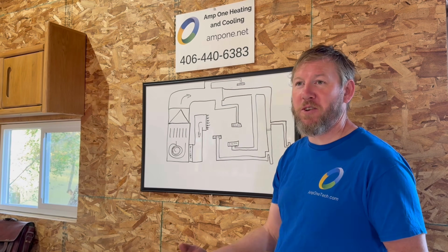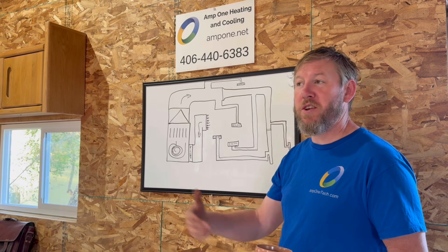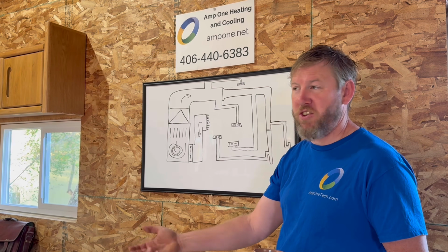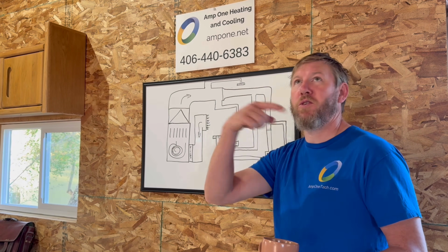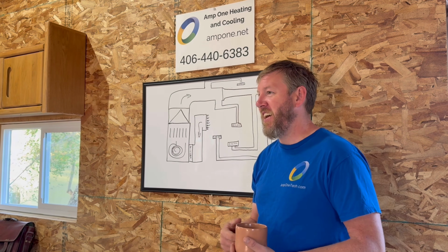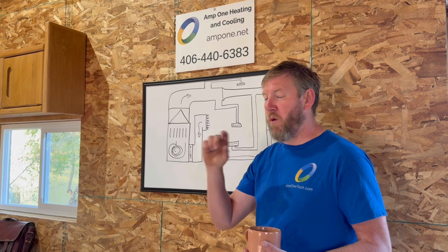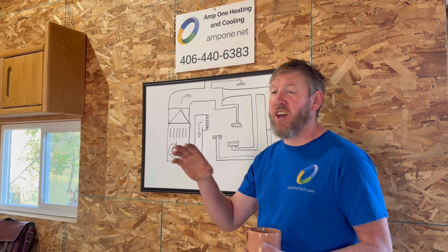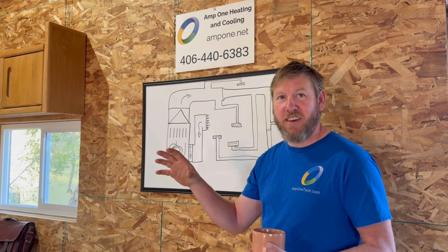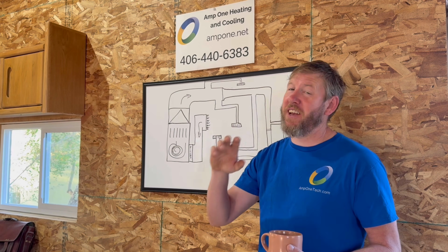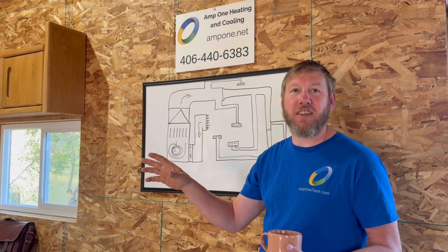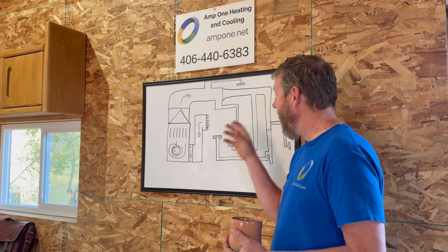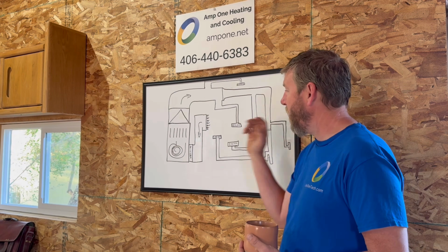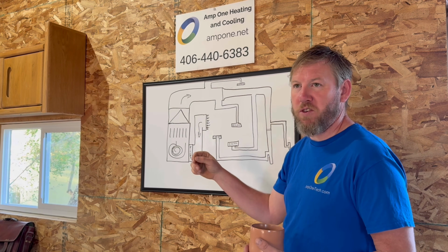Okay, yeah, we were talking about superheat, subcooling, and the reasons we want the superheat, just a review from 2 days ago. We want a certain amount of superheat, and it does change if you have a TXV, which I know you're not a fan of, but they're going to be on everything here soon with all the efficiencies. And then it'll be a little higher if you've got a fixed orifice.